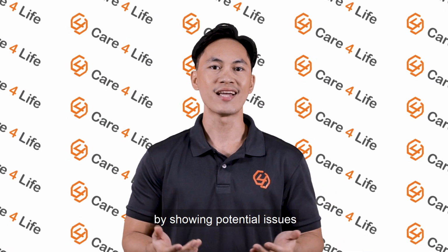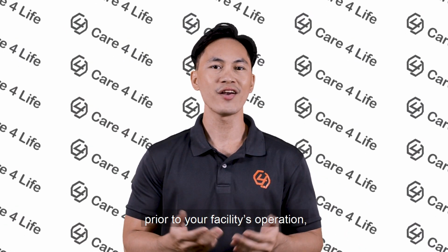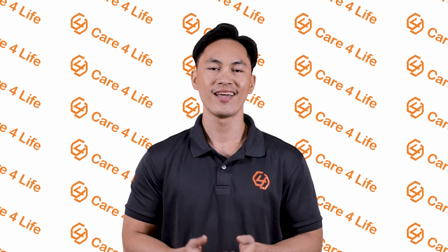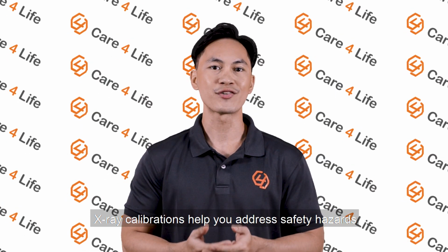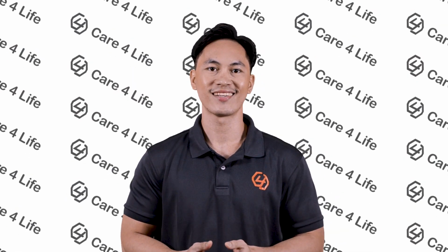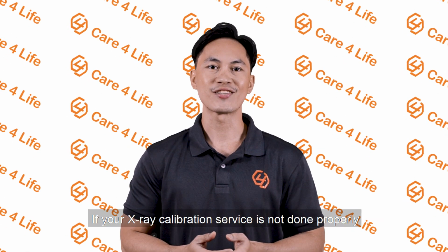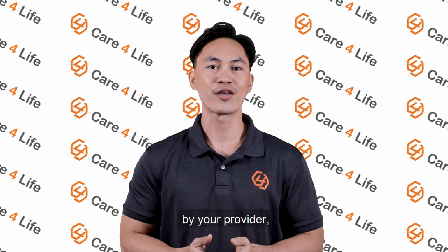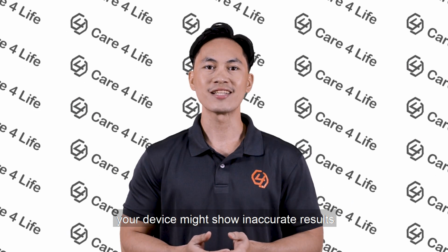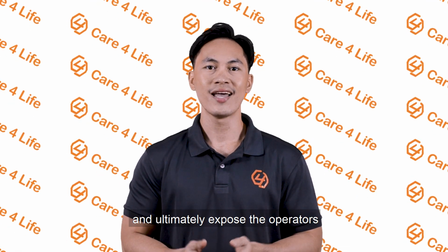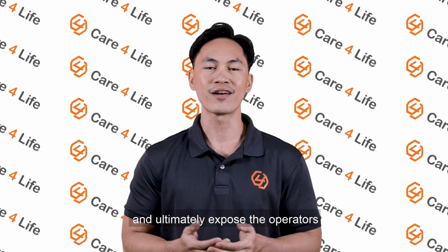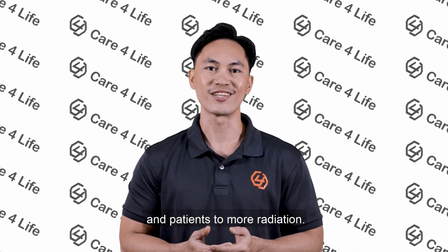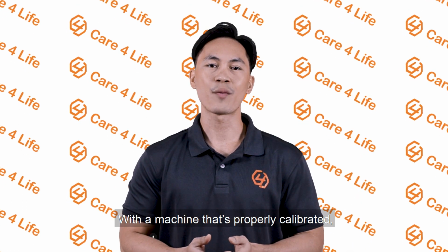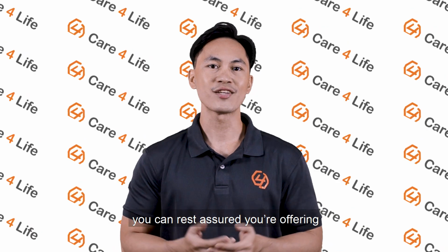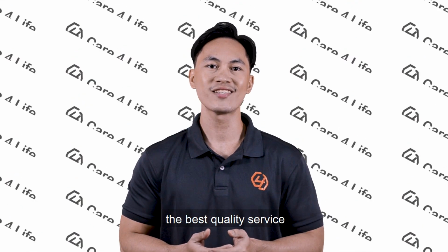Furthermore, by showing potential issues with your unit prior to your facility's operation, X-ray calibrations help you address safety hazards efficiently. If your X-ray calibration service is not done properly by your provider, your device might show inaccurate results and ultimately expose the operators and patients to more radiation. With a machine that's properly calibrated, you can rest assured you're offering the best quality service for your patients.